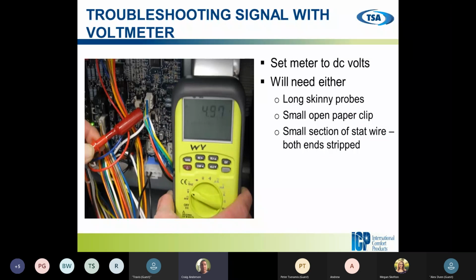So if we're going to use a voltmeter, you're going to make sure that you have a voltmeter that's going to check DC voltage that is fluctuating. You're going to need long, skinny probes because we want to get in the back of the plugs. If you don't have long, skinny probes, couple things to do. If you have a paper clip, you can get a paper clip shoved in there and you can test off the paper clip. Stat wire works as well. Strip both ends, get your stat wire, jam it in there, and then you can test off that stat wire. So make sure you take it out after you're done with it. If you got long, skinny probes, then you're done.